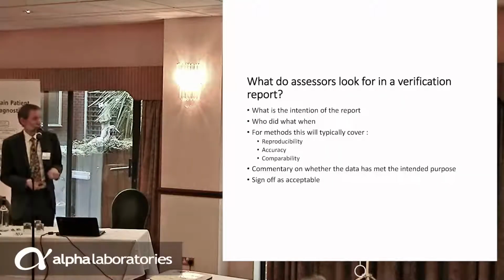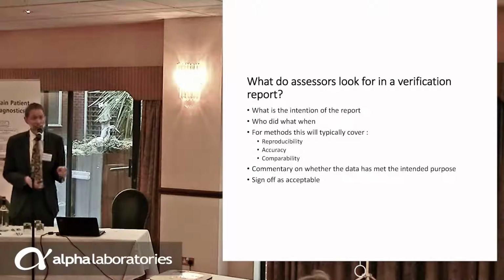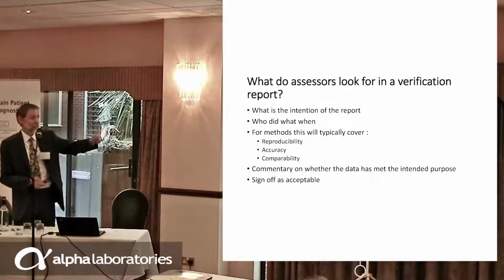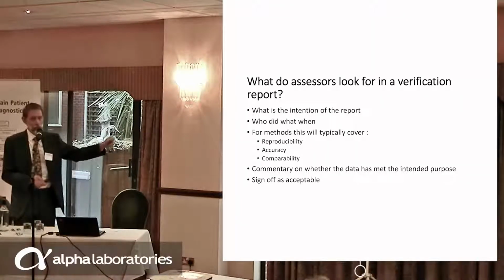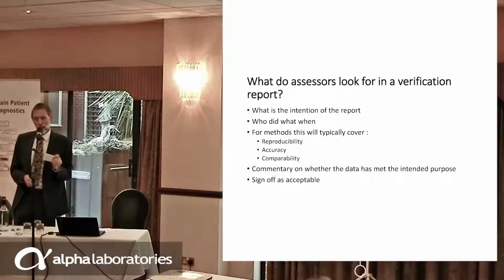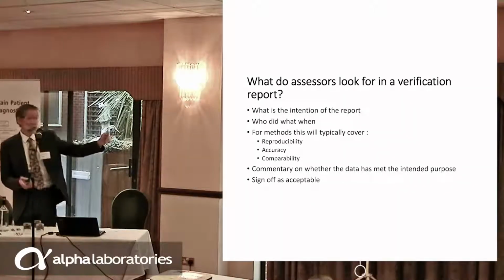And key things that I think are important to put in are data on reproducibility, on accuracy and comparability. I would like then that data to be reviewed with a commentary on whether the data has met the intended purpose. So you said what you're going to do, and now you're going to present some data and say, yes, it has met the intended purpose that I've defined. Very important to say, if you look at method comparisons, no two methods agree, do they? Has anyone found any methods that agree totally? They're always different. So you've got to put that commentary on.